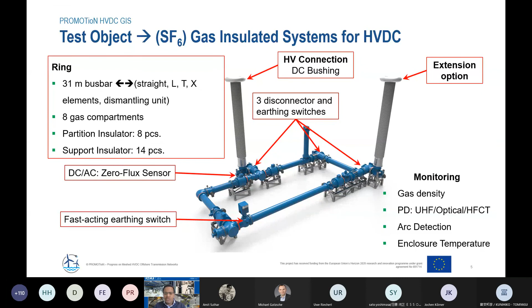There is also an RC divider on board, as you see here. And there is also switching equipment: 3 disconnectors and an earthing switch. There is a fast earthing switch in this location. And of course, many other monitoring measurements, for example, gas density; partial discharge monitoring on board was also available. Different technologies have been used, arc detection, and temperature monitoring of the enclosure has also been included.